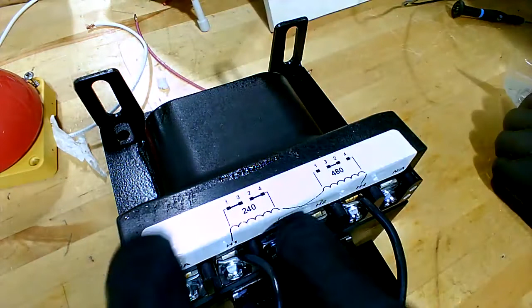If you got 480 coming in, well, that's what you have coming to the machine. If you got 480 across the outside terminals, you put a single jumper in the center, and it links the center two together, and you're sharing 480 volts across two of those. Those two share half apiece. You end up with 240 across each winding when you put a single jumper in the middle, but it makes it a series. With 480 across the two in series, each one actually bears 240. It's kind of like two people sharing a plate of food. You know what I mean?